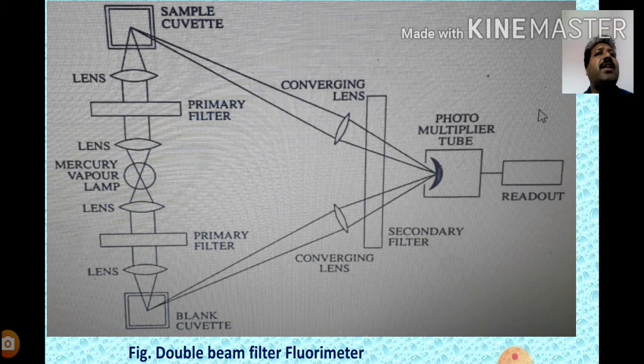In more sophisticated spectrofluorimeters, grating monochromators are used instead of filters to ensure the dispersion of light into individual wavelengths. A high pressure xenon arc is used as a source of radiation. The electron current produced in the photomultiplier tube is amplified and the amplified electric signal is sent to a readout device. This amplification enables the detection of small amounts of substances whose fluorescence is very low. Hence, spectrofluorimeters can be used for the sensitive and fast analysis of trace materials in samples.